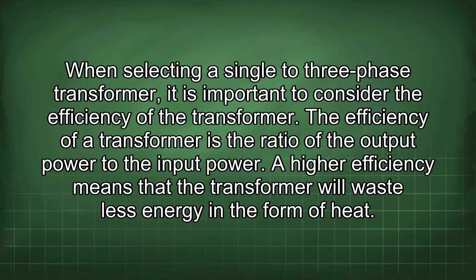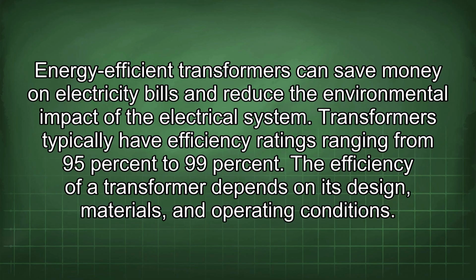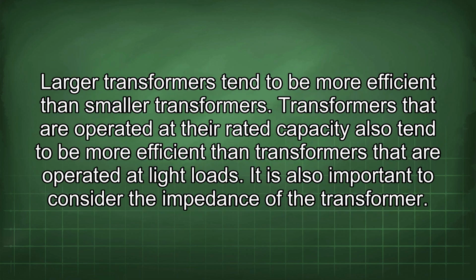When selecting a single to three-phase transformer, it is important to consider the efficiency of the transformer. The efficiency of a transformer is the ratio of the output power to the input power. A higher efficiency means that the transformer will waste less energy in the form of heat. Energy-efficient transformers can save money on electricity bills and reduce the environmental impact of the electrical system. Transformers typically have efficiency ratings ranging from 95% to 99%. The efficiency of a transformer depends on its design, materials, and operating conditions. Larger transformers tend to be more efficient than smaller transformers. Transformers that are operated at their rated capacity also tend to be more efficient than transformers that are operated at light loads.